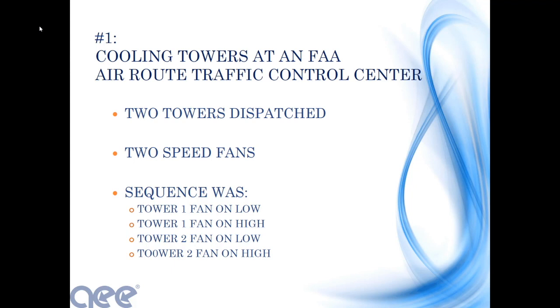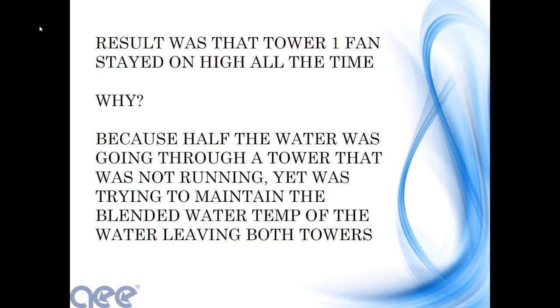Well, with only 1 chiller online and having a whole lot of flow, that's why they had to have 2 cooling towers. The water going through the 1 cooling tower now is not being cooled at all. So the other tower now is trying to compensate for that. And what we ended up with was that the fan on Tower 1 ended up being on high speed all the time, even though there wasn't enough load to really require 1 cooling tower. It was beating itself to pieces trying to maintain a condenser water temperature, and all this other flow is going through a machine that's not working and basically defeating its purpose in life.